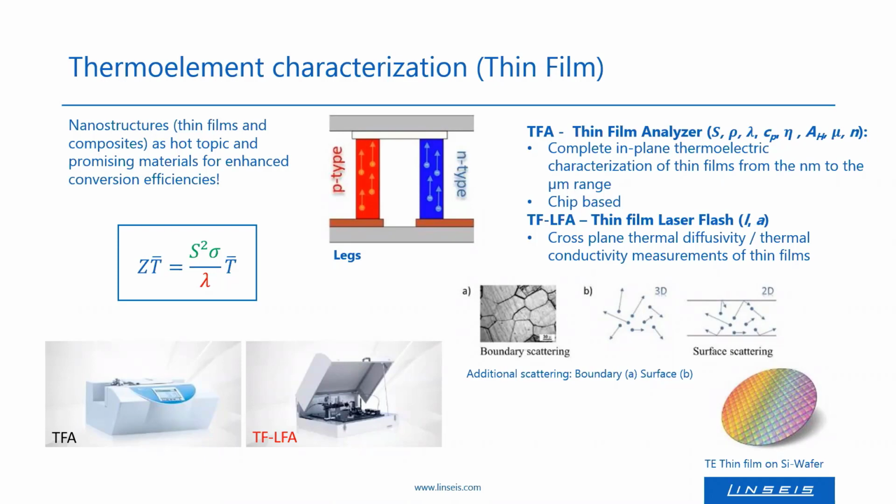There's the thin film laser flash analyzer, here shown on the right. This one can measure the cross-plane thermal diffusivity, similar to the LFA, but especially for thin films from the nanometer to the micrometer range.